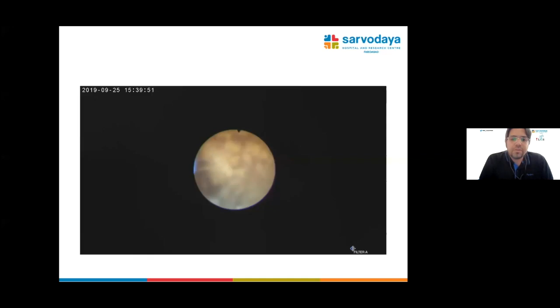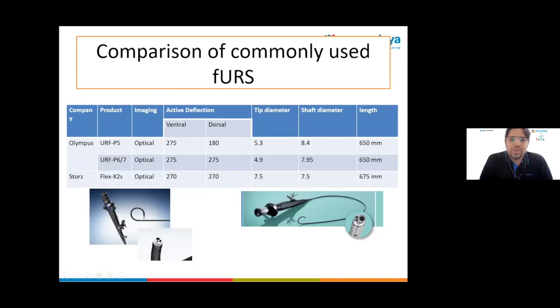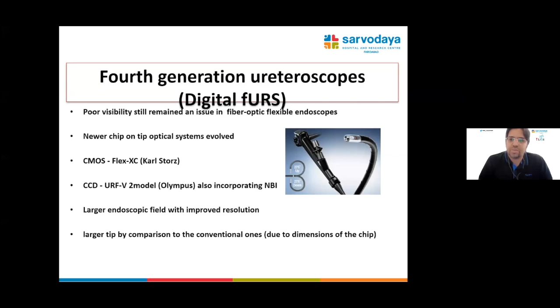So this is just a chart comparing the two, and as I mentioned, the main difference is that there is a taper in the diameter in P6 and P7, whereas in Karl Storz there is a uniform diameter. It is on your personal preference which type of scope you would like. But as we know, poor visibility still remained the issue with fiber optic scopes. So newer chip-on-tip systems evolved. Karl Storz came with the CMOS system and Olympus came with CCD chip-on-tip. The advantage was a larger endoscopic field with improved resolution, but the larger tip by comparison to the conventional one added to the size of the scope. So they are generally thicker than the fiber optic scopes.